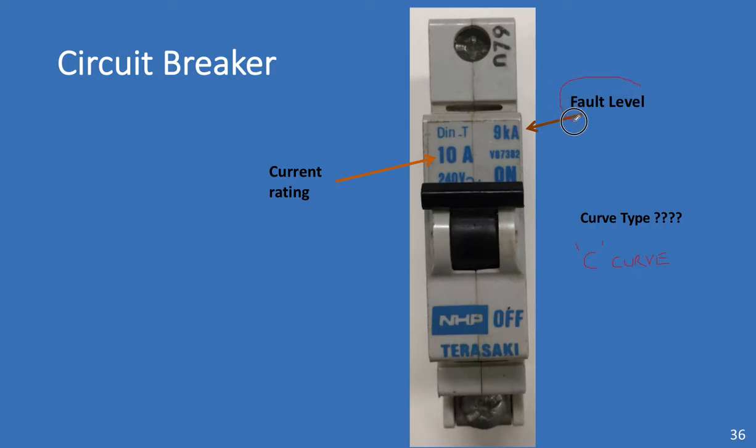Now, the fault level. What this 9,000 amps is telling us is that the electrical and mechanical strength of this circuit breaker is, it will handle 9,000 amps for one second. If you try and put 9,000 amps through it for a second and a half, it will physically fail. It will heat up. It will melt. It will explode, depending on how much above 9,000 amps you go.